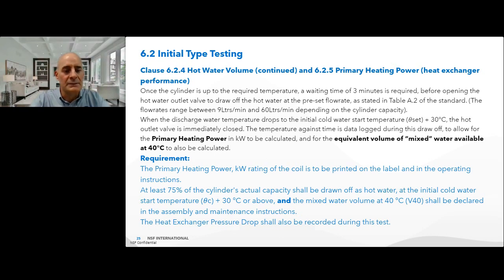At least 75% of the cylinder's actual capacity should be drawn off as hot water at the initial cold water start temperature, theta C plus 30 degrees C or above, and the mixed water volume at 40 degrees, V40, should be declared in the assembly and maintenance instructions. Also, the heat exchanger pressure drop should be recorded during the test.